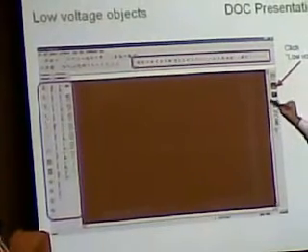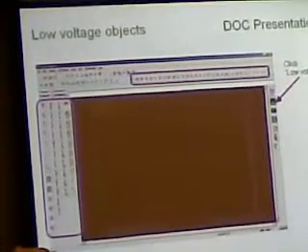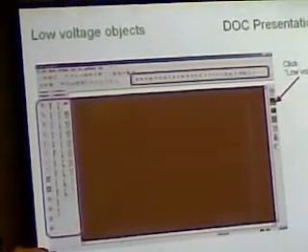And this is to get the time current characteristics for breakers. You will get time current characteristics for the breakers. Maybe those characteristics are required to justify what the setting range is and what the setting level is. Maybe we can justify the coordination also in a different method.